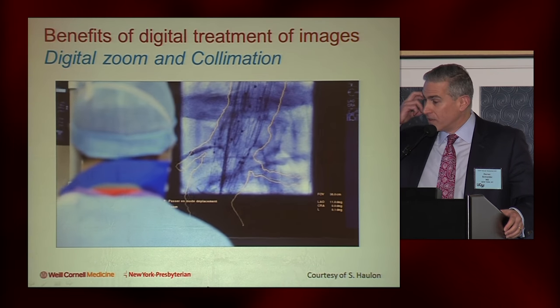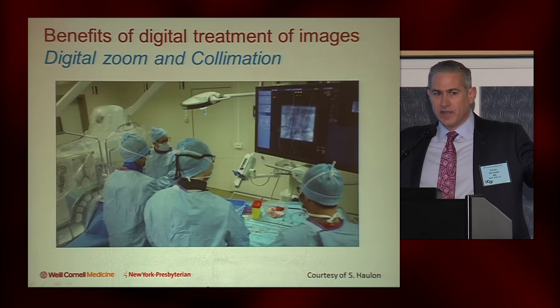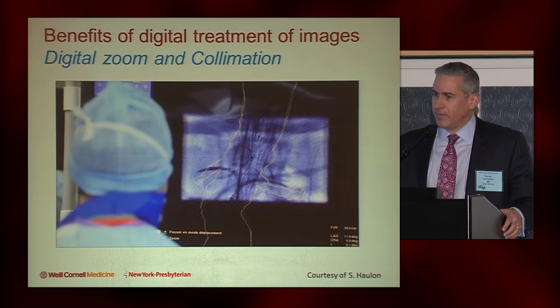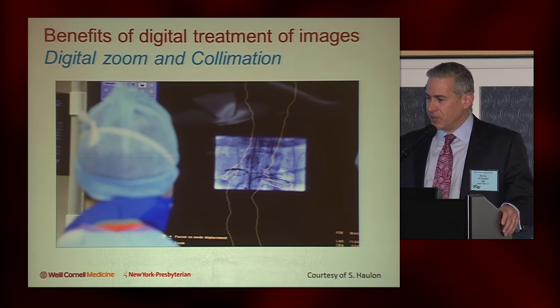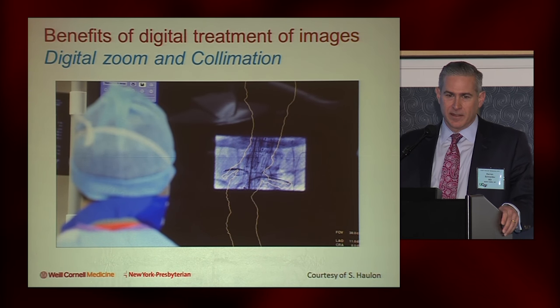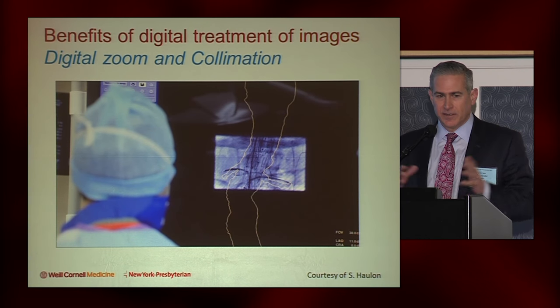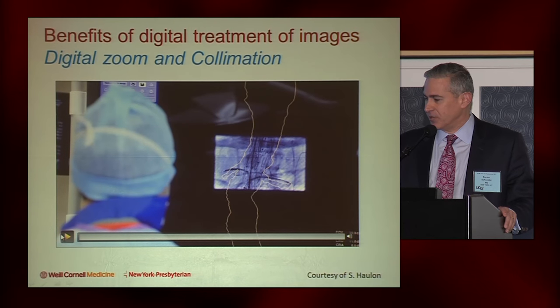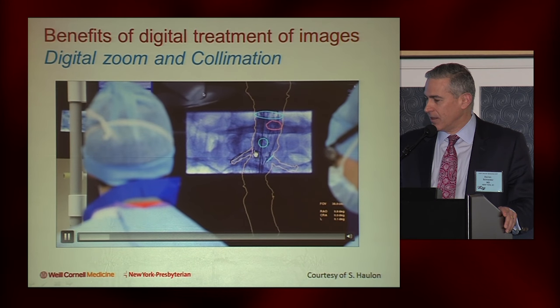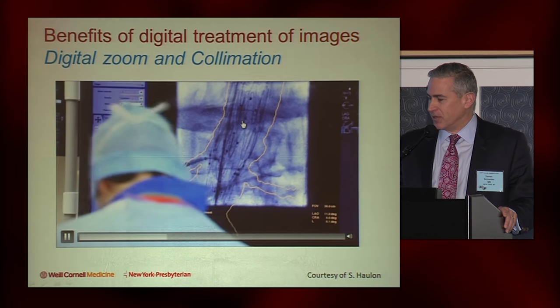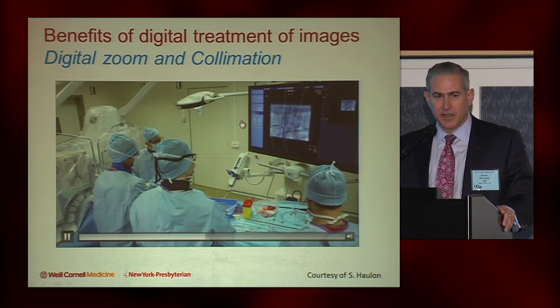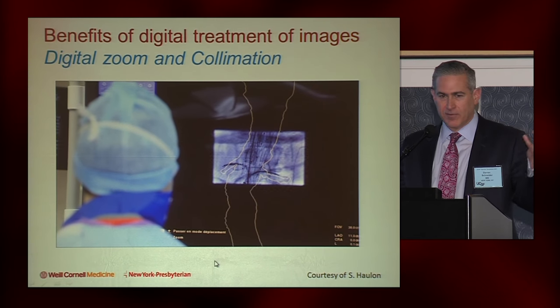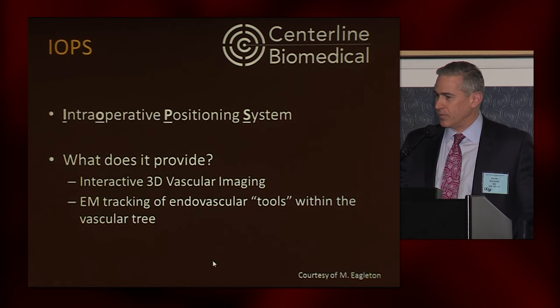This is the concept of digital zoom. Nowadays we have very large high-definition monitors on the new machines, so rather than magnifying up the actual fluoro and using more radiation, you can collimate, take that non-mag image, and then digitally enlarge it on the screen — and that saves additional radiation. You can mag up the image on the screen without changing the radiation dose and magnification on the machine itself, giving you great resolution to still do all of these detailed procedures.